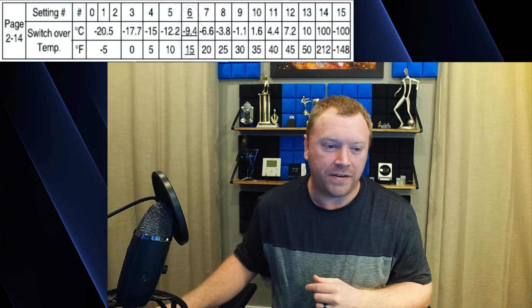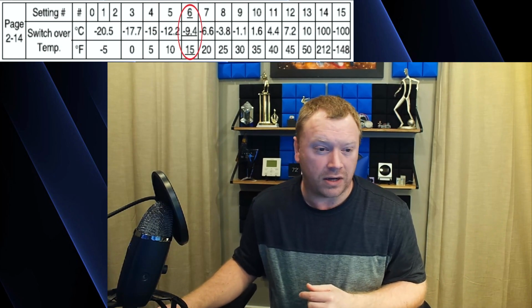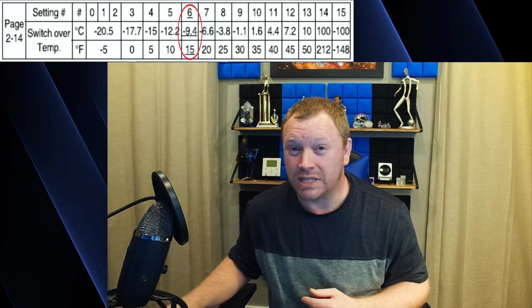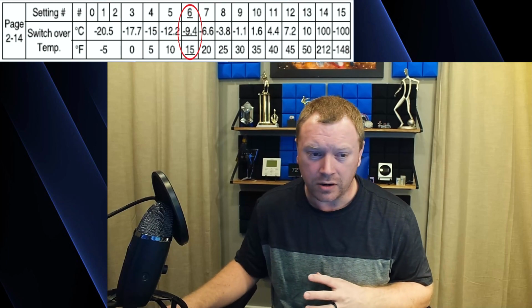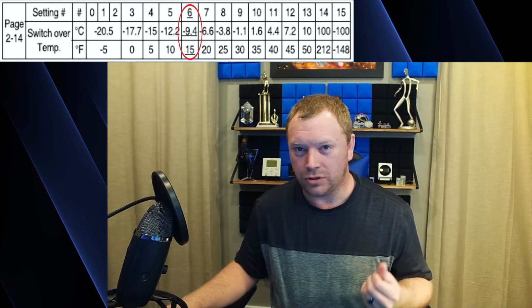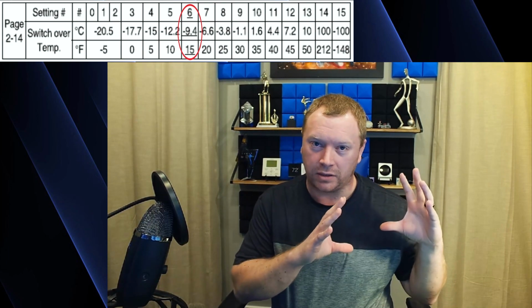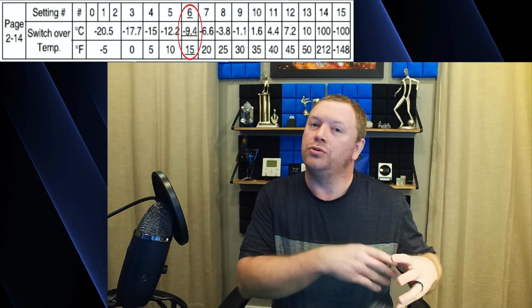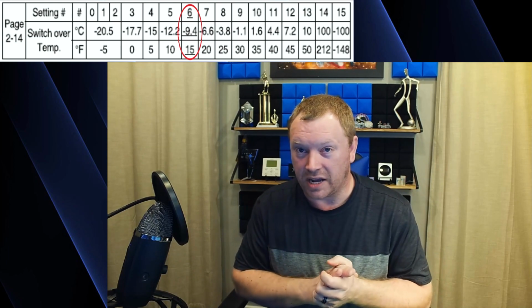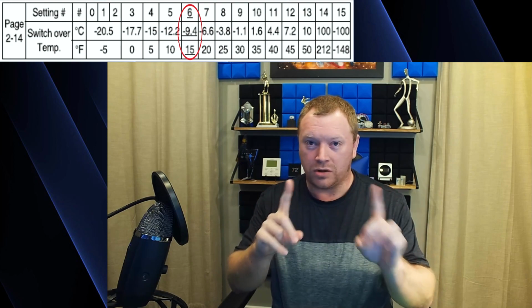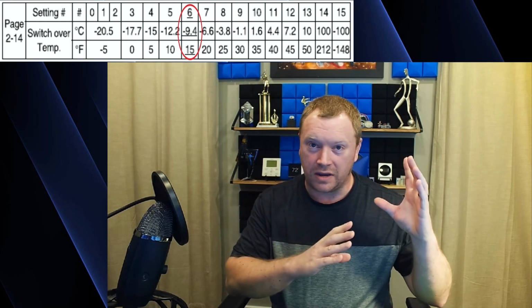So out of the box, at least today, your balance point is set for 15 degrees Fahrenheit. It's going to be minus 9.4 degrees Celsius for any of you Celsius guys out there. But at 15 degrees outdoor temperature, the heat pump is going to automatically shut down, change over, and operate the gas furnace. And that's when you have a one-to-one gas furnace indoor and outdoor application.